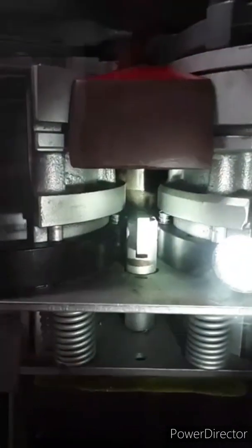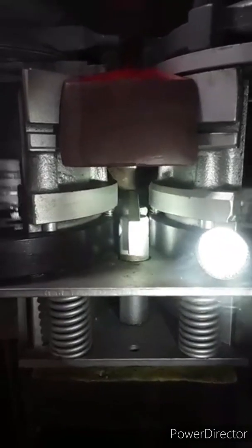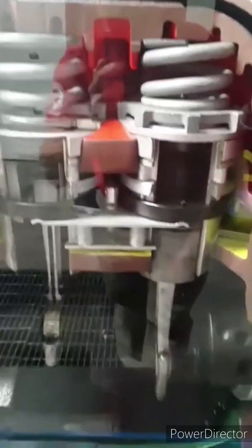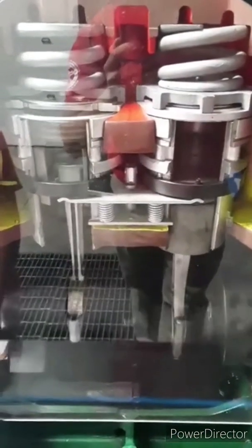Adler's going to load it up for us — watch that piston in the back. As we load and unload, with that oil pressure established on this machine — it could be pneumatics as well — you'll see the suction sealing ring back here. When it's around the slots of the cylinder sleeve, we're in compression. When it's lifted off the springs down here, we are completely unloaded. Pretty neat what's happening here.